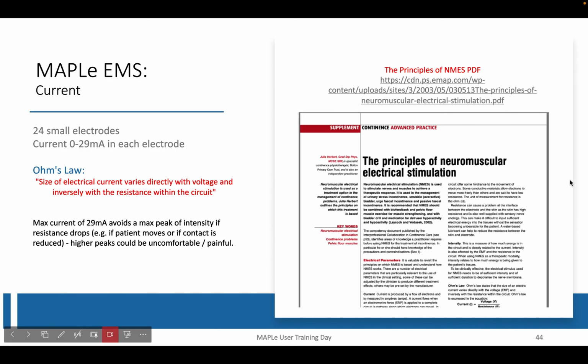But because there are 24 very small electrodes, the surface area is quite great. And Ohm's law states that the size of the electrical current varies directly with voltage and inversely with resistance within the circuit. So the capping of the milliamps at 29 is for your patient's safety, so that if they do move or if contact or connection changes, there won't be a surge of electrical input into that pelvic floor causing pain or heat. So the maximum current is set at 29 milliamps for any electrical stimulation with Maple.